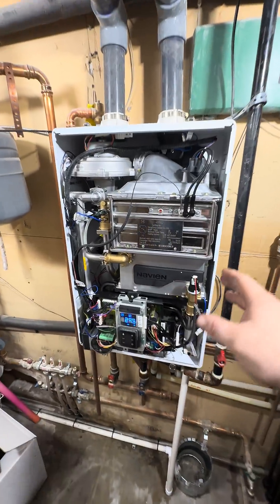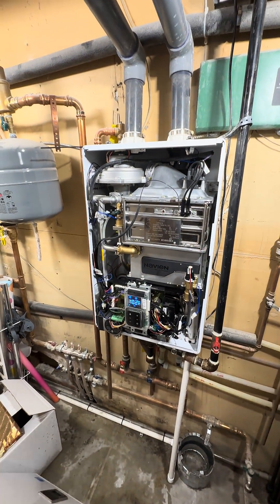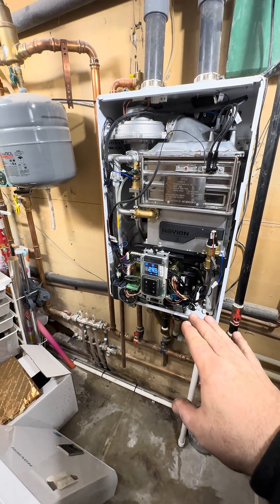Just replaced this NCB heat exchanger — it's up and running, you can see the fire in there. Was fully sooted up. The venting on the outside was wrong, and programming still needs to be verified.